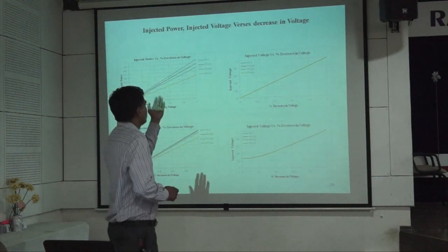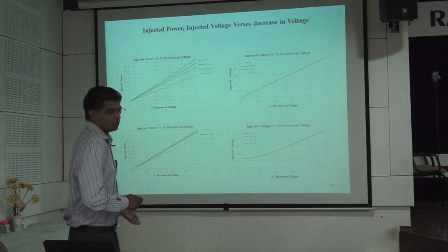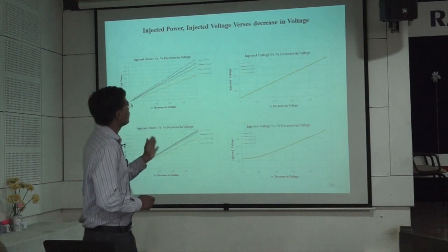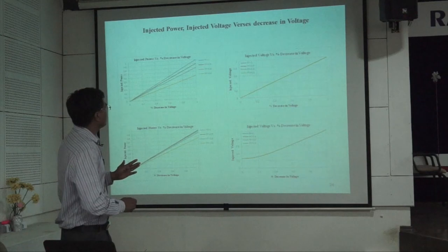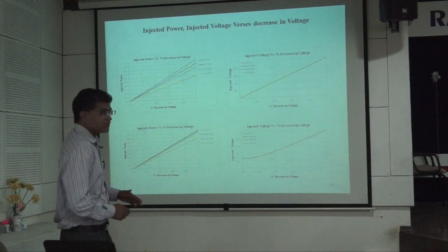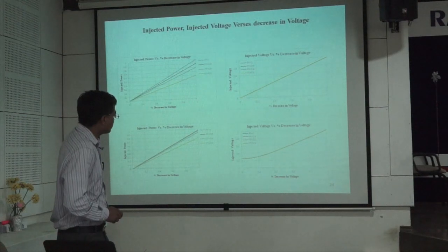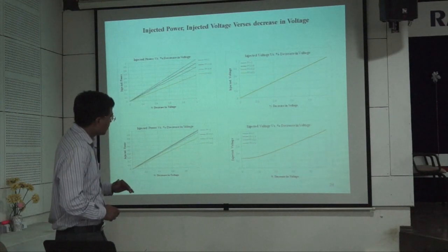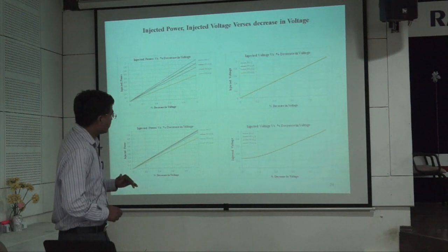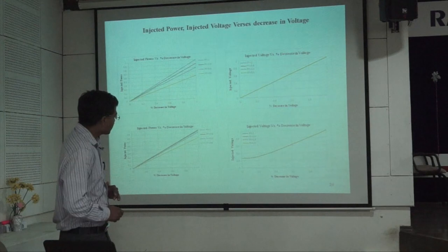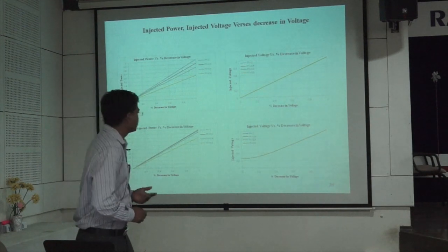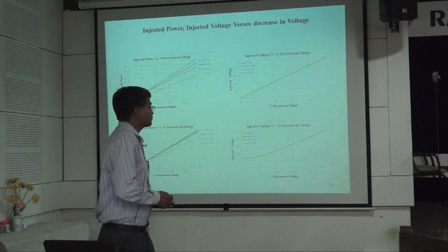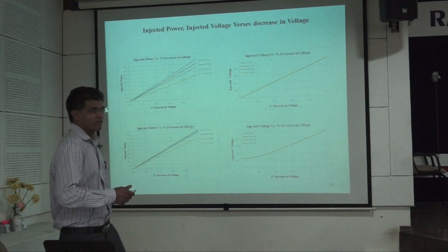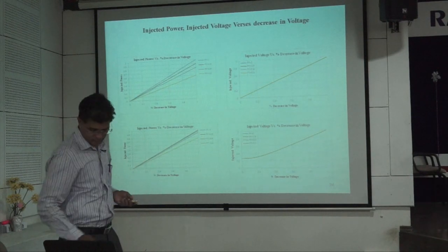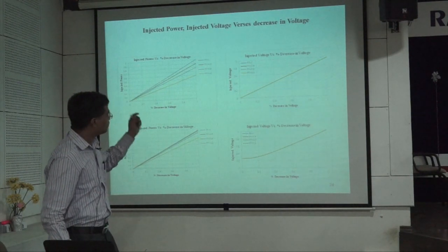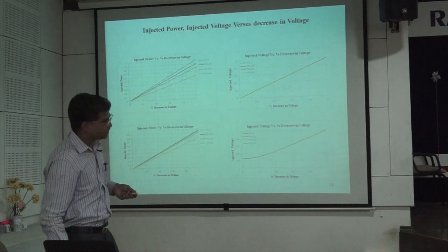For all the cases, it does not depend on the power factor of the load. Whatever the power factor may be, the injected voltage will remain constant for any power factor. But if there is a phase jump, with a 20% decrease in the voltage, the injected voltage will be higher. For a 10% decrease in the voltage, you have to inject around 29% voltage in the system. That means there is a higher voltage injection. That's why we need a higher rating of the DVR, and that's why the cost of the DVR goes on increasing. That's why we have to minimize this. There should be a minimum phase jump in the system.